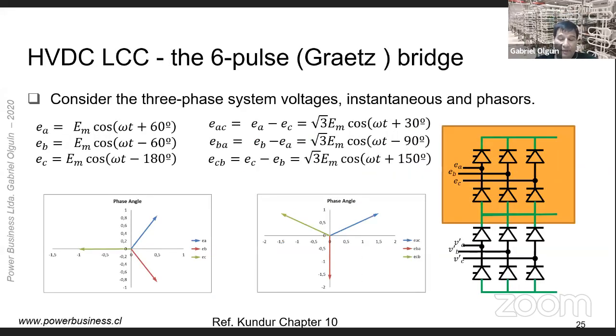Okay, let's get into the mathematics. Let's review the operation of the LCC HVDC converter. As I said, a practical HVDC converter uses 6-pulse controlled converters in series on the DC side, fed in parallel from the AC side. However, to understand LCC HVDC converters, we need to review the operating principles of the 6-pulse 3-phase bridge. We will first review the 6-pulse uncontrolled converter based on diodes, and then introduce the gate control that is possible thanks to the thyristor valve.